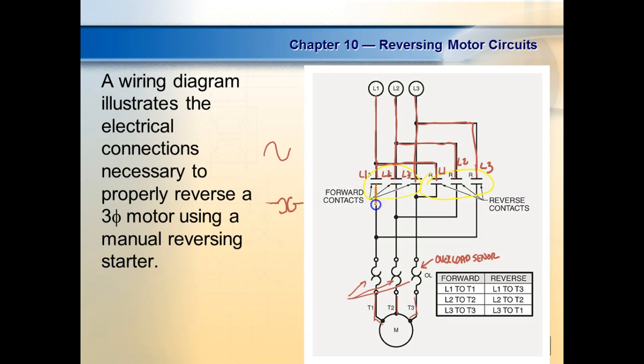So we bring this first one, the one that's on your left, or the one directly above the motor, and you bring this straight through. So we're going to bring L1 to T1, L2 to T2, and L3 to T3. Now coming from the other way, here's L1. On the other side, we're going to jump this over to what? T3. That's going to swap it, right?